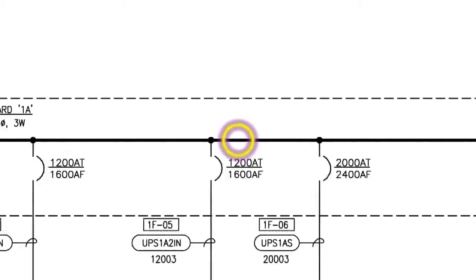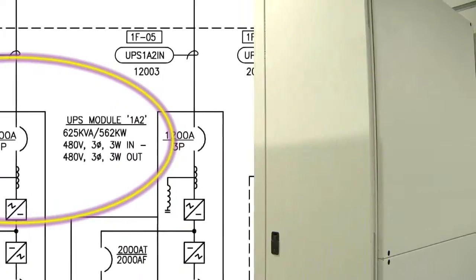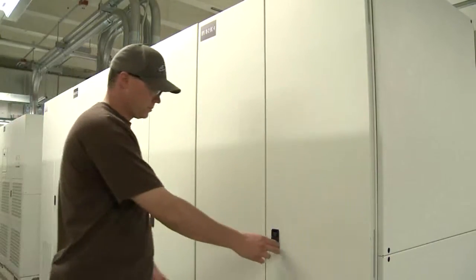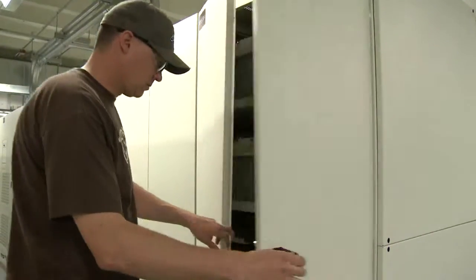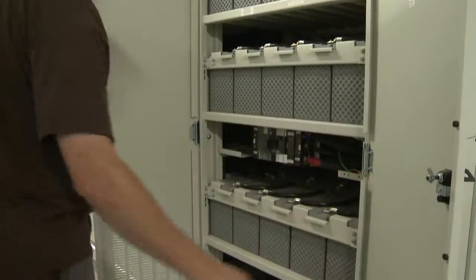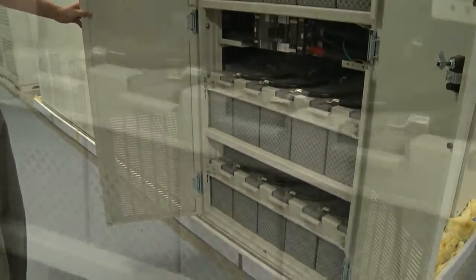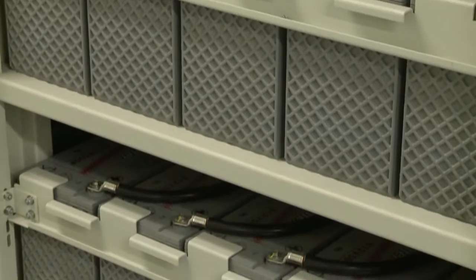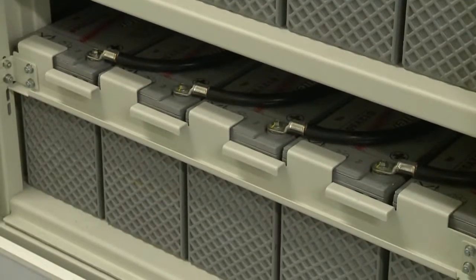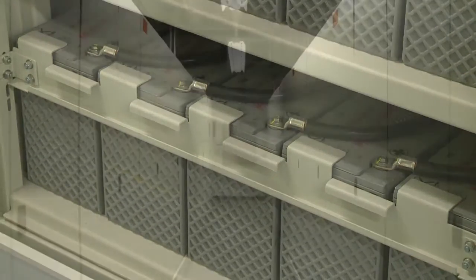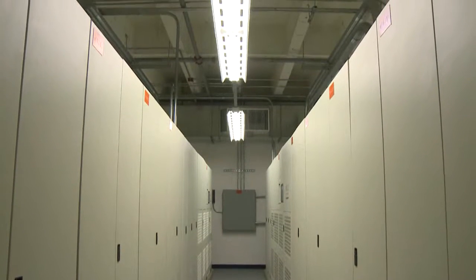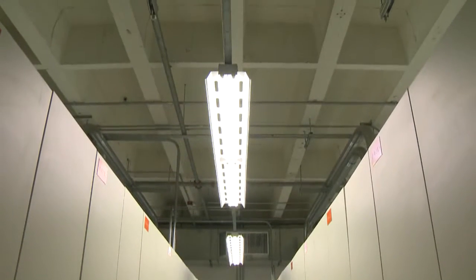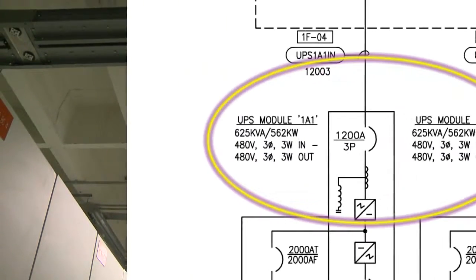The uninterrupted power supply, or UPS, is a system that keeps the servers powered during the initial transfer from utility service to generator supply. During a utility outage, the load is transferred to the UPS system until the generator system starts and provides the voltage and amperage to the main switchboard. The UPS does not carry mechanical or lighting loads during the transfer or during normal operations.